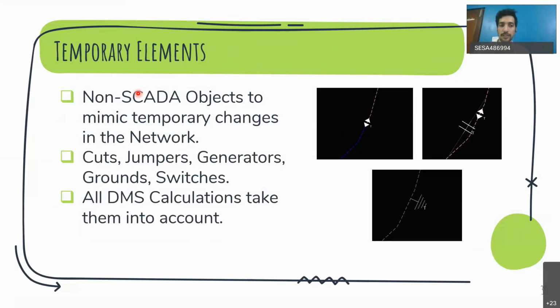Next one is temporary elements. These are nothing but non-SCADA objects to mimic temporary changes in the network, for example fiber cut, tree fall, or use of a jumper because of some temporary scenario. All those things obviously won't be SCADA for conductors, so they cannot be automatically mimicked in the control center. But with the help of these temporary element objects, you can manually create them. For example, you can manually place a cut in case of a tree fall to denote that the conductor has been cut at that point in the network. Similarly for other types: jumpers, temporary groundings, temporary generators, etc. All calculations take these into account as well.